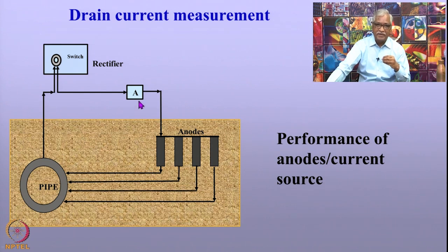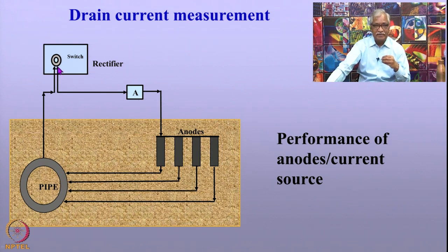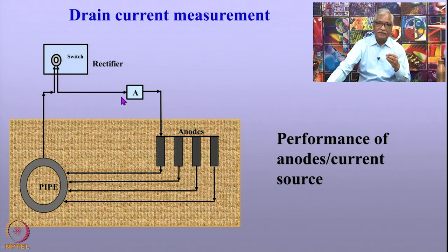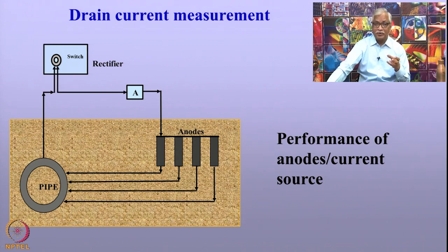The technique used to measure the drain current is relatively simple: insert an ammeter in series in the circuit. At a test station, there is a rectifier in the case of an impressed current system. If it is a sacrificial anode system, you connect the ammeter in series between the pipeline and the anodes, and the current is measured. The current so measured gives an indication about the performance of the anodes or whether anode resistance has increased.